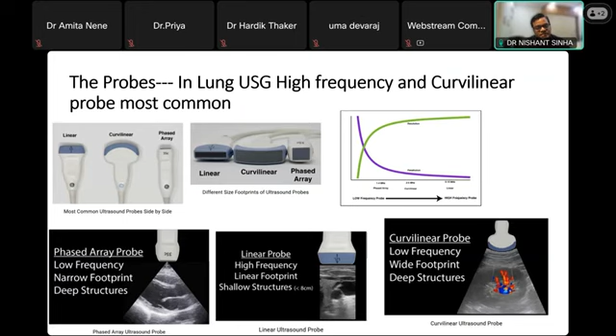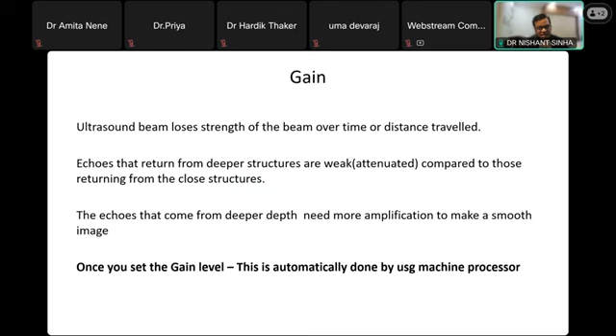So gain is basically done by the machine. It helps us to amplify the deeper reflected waves more and the superficial reflected waves less. The machine mixes all this and gives it to us as the final signal, which is called grayscale. I'll come to that in the next slide. Next. So this is the exact picture showing the same. If you plot on the x-axis distance from the transducer, and on the y-axis amplitude of the reflected signal, you see very carefully that if the signal is coming from 5 centimeter depth, it is more amplified by the machine itself, and that's how the grayscale comes.